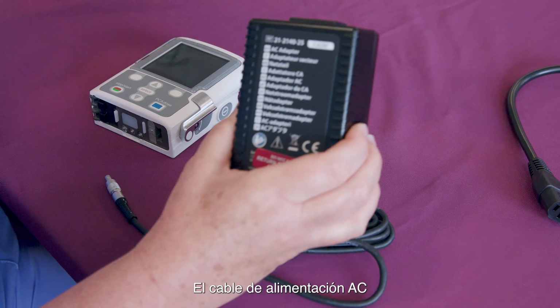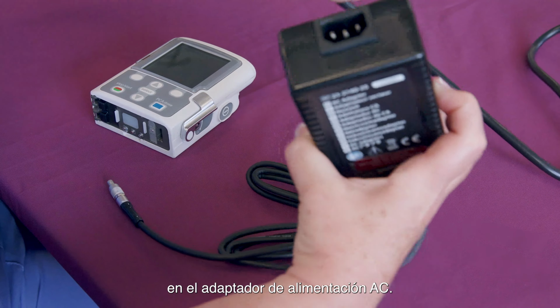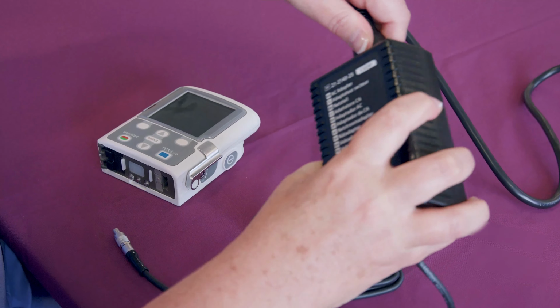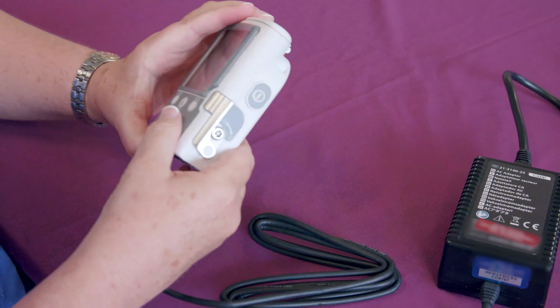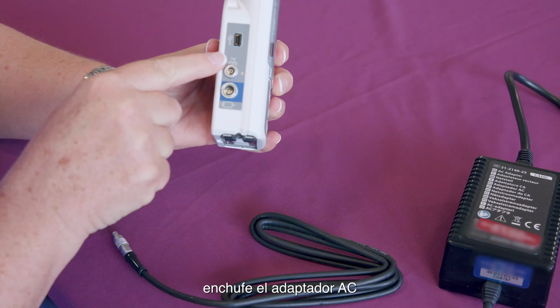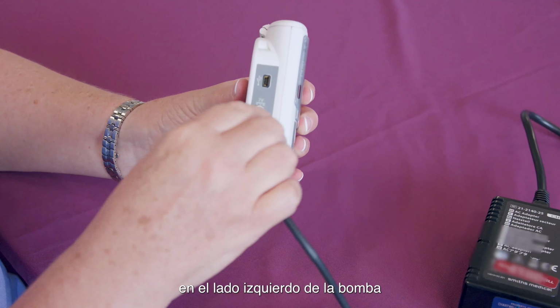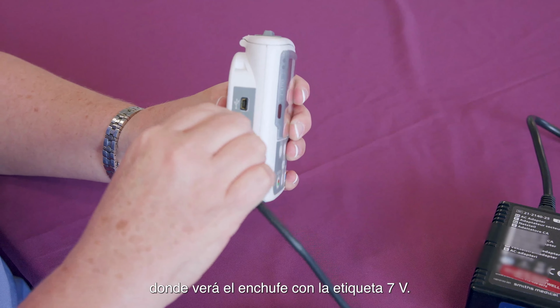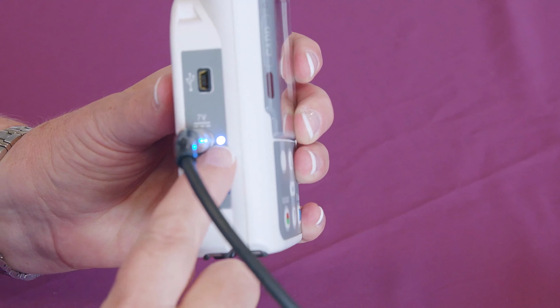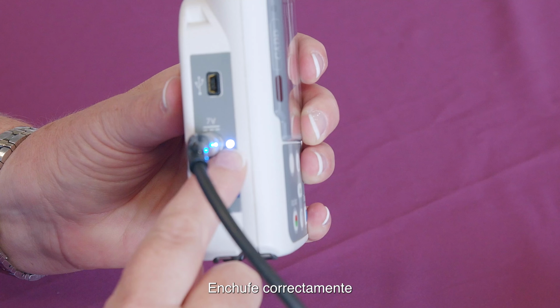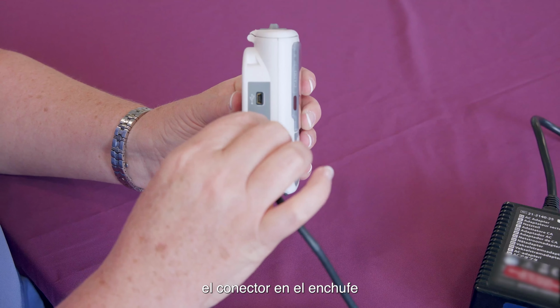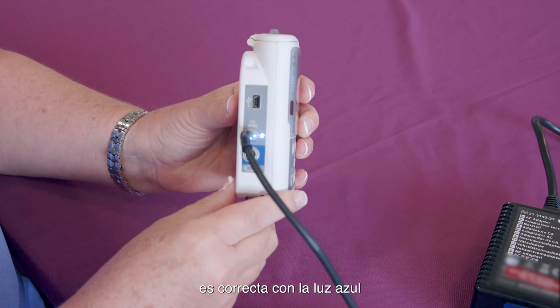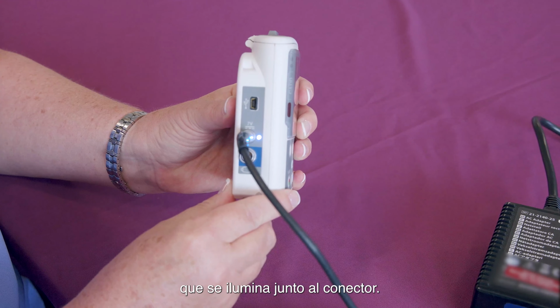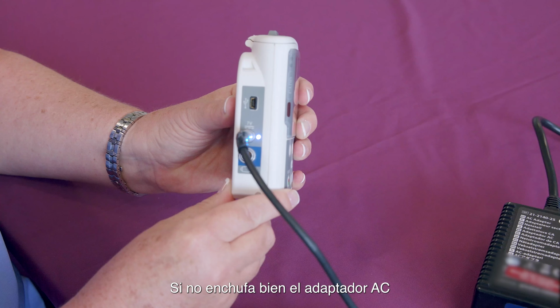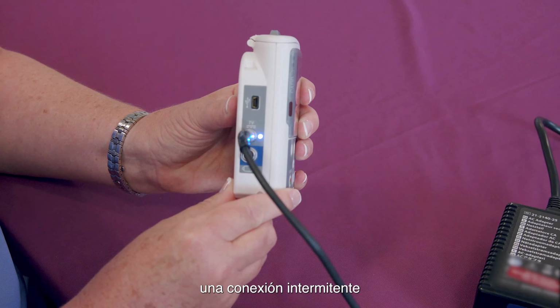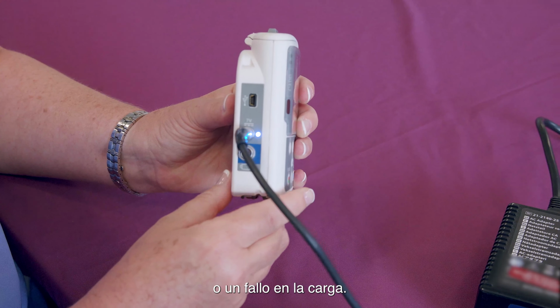The AC power cord must first be plugged into the AC power adapter. Next, plug the AC adapter into the pump's AC power jack on the left side of the pump labeled 7V. You must plug the connector firmly into the power jack and confirm a proper connection indicated by the blue light next to the power jack. Failure to push the AC adapter all the way into the power jack may result in intermittent connection or power failure.